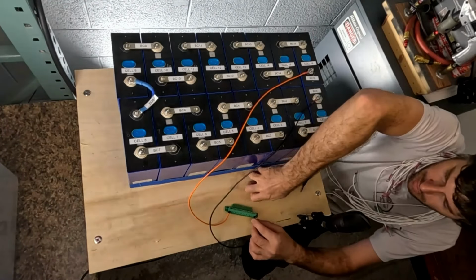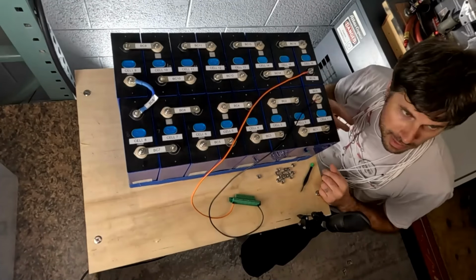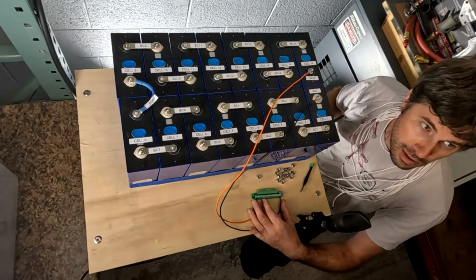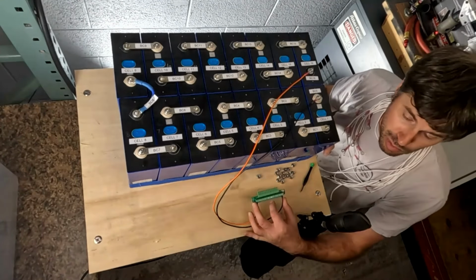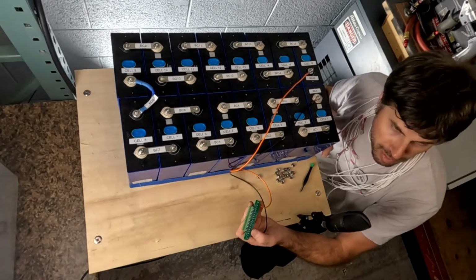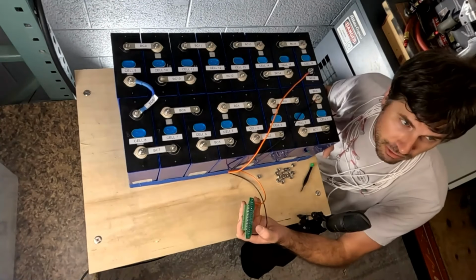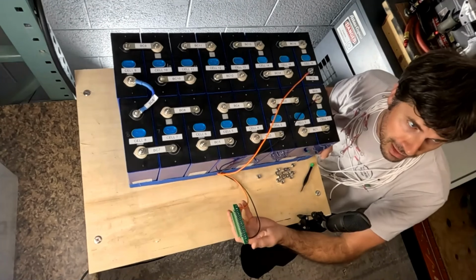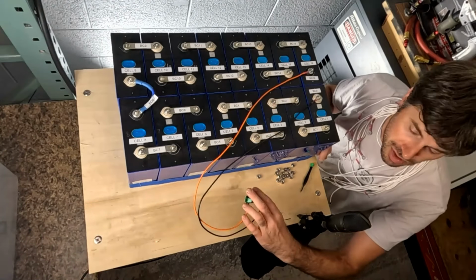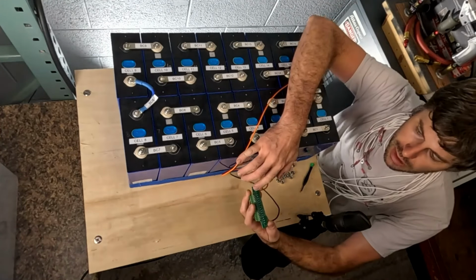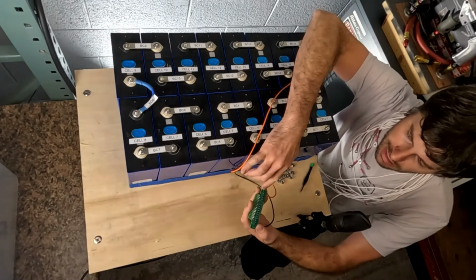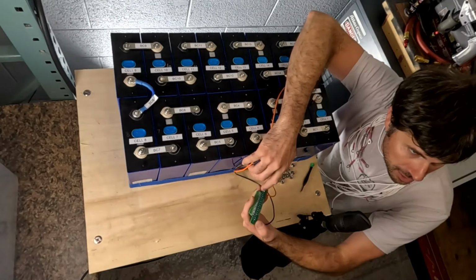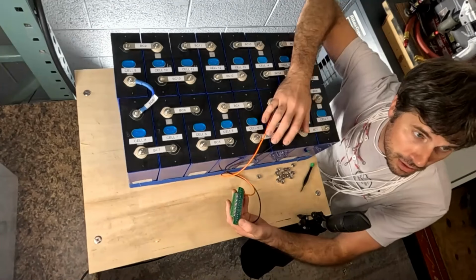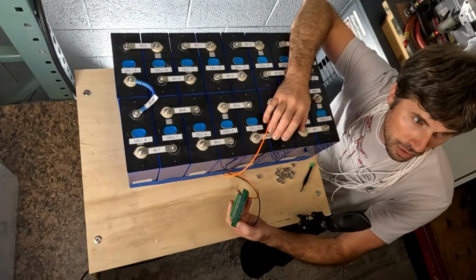I'm going to keep going like this and attach all of my balance wires one at a time. One thing you need to be careful of is the pins on the back of the balance wire terminal board. If you sit these down on top of a metal tool or metal work surface, you could cause a short circuit between two cell connections, which would burn out the traces on this board. If that happens, you can request a new terminal board from Overkill Solar and we'll replace it.